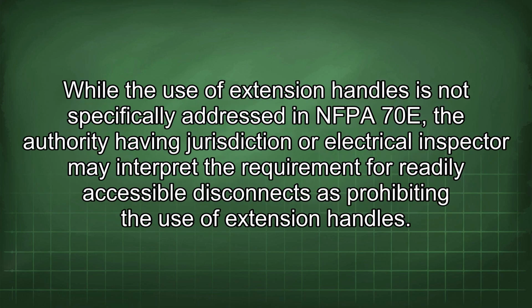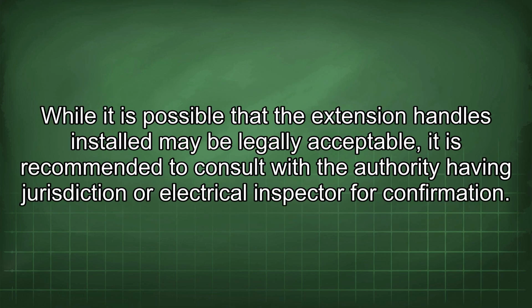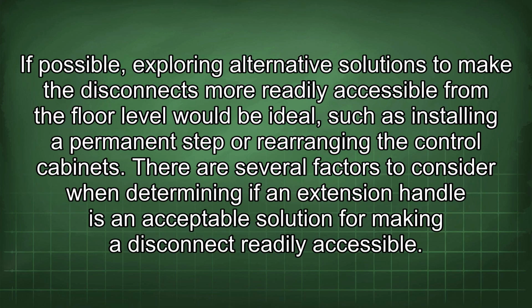While the use of extension handles is not specifically addressed in NFPA 70E, the authority having jurisdiction or electrical inspector may interpret the requirement for readily accessible disconnects as prohibiting the use of extension handles. While it is possible that the extension handles installed may be legally acceptable, it is recommended to consult with the authority having jurisdiction or electrical inspector for confirmation. If possible, exploring alternative solutions to make the disconnects more readily accessible from the floor level would be ideal, such as installing a permanent step or rearranging the control cabinets.